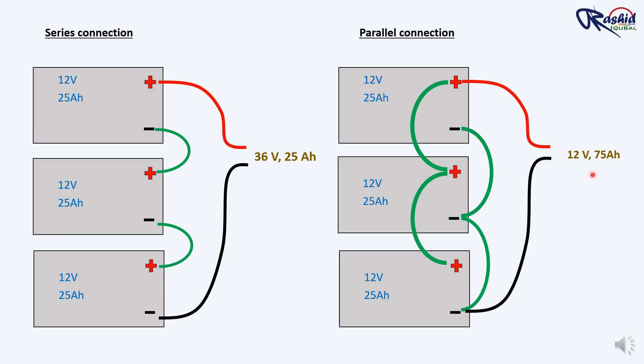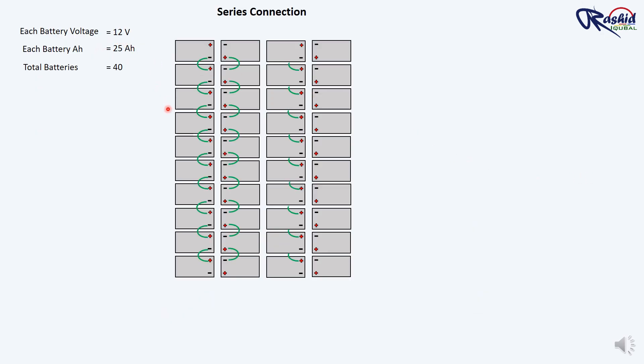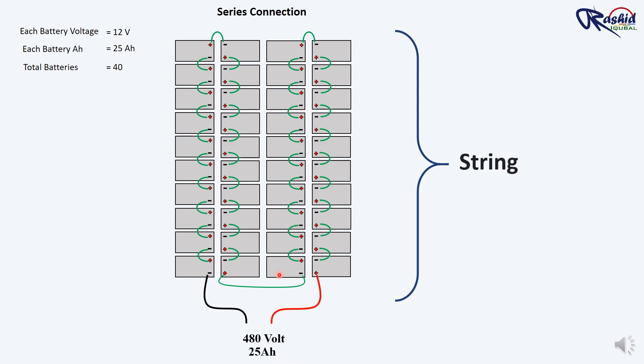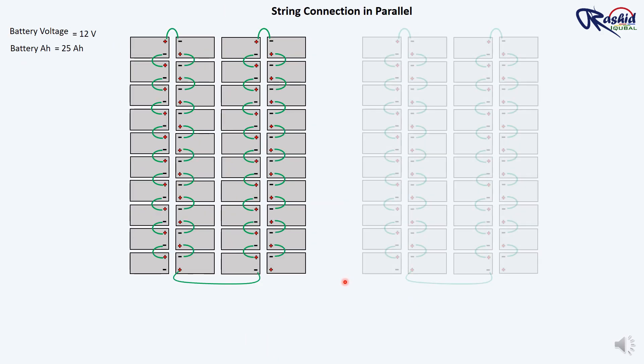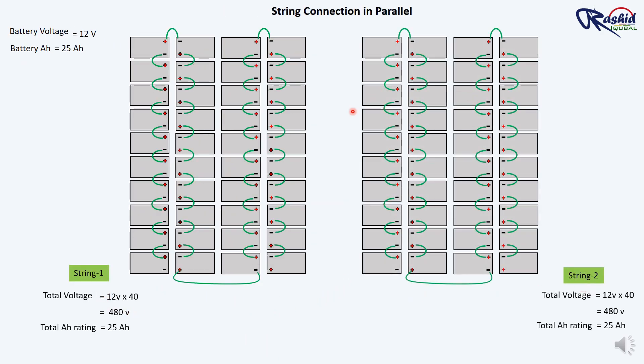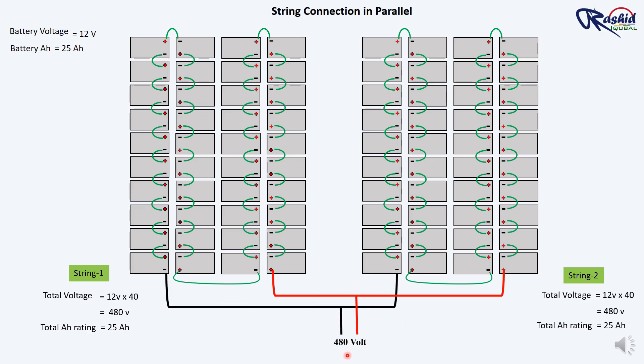Here you can see how 12V batteries are connected in series to increase the overall voltage. A total of 40 batteries are connected in series to achieve 480V — this is the benefit of series connection. When you connect multiple batteries in series like this, it is called a string in a UPS. To increase capacity or AH rating, you connect multiple strings of batteries in parallel. The positive terminals of all battery strings are connected together, and the negative terminals are also connected together, so voltage remains the same while capacity increases.